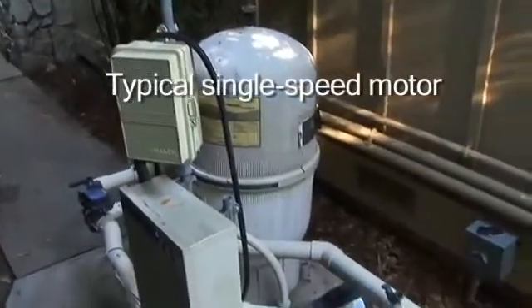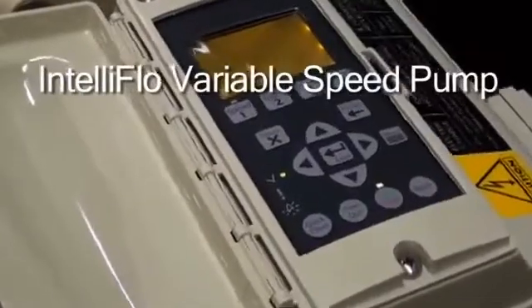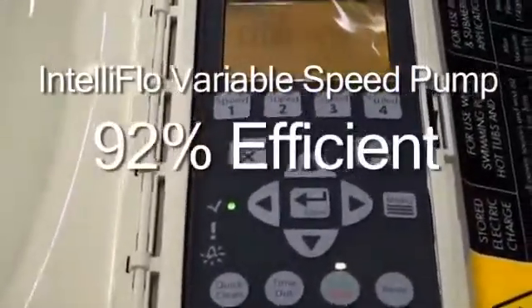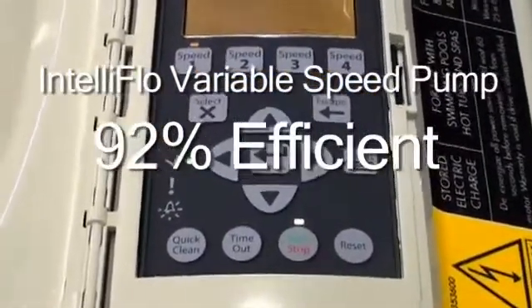The standard single speed pump on a pool today is about 40 to 70 percent efficient. The IntelliFlo uses a permanent magnet motor and the efficiency of that motor is about 92 percent. So that means a conventional single speed motor is wasting as much as two thirds of the energy that goes into it. That's right, Steve.